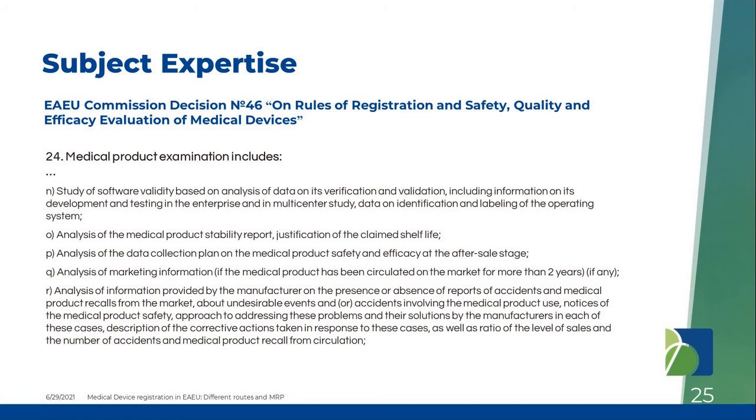Here, if your medical device contains software, you should provide the documents of the software validation. All the documents related to the software validation process should be provided. And please pay attention to point P, analysis of the data collection plan on the medical product safety and efficacy at the post-marketing stage. So they are talking about the post-market surveillance plan.